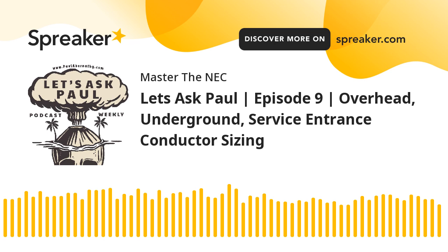Now, ironically, somebody said to me, Paul, what if I have no continuous loads and no conditions of use, no adjustment or corrections involved? Then you simply size your conductor based on your calculated load, and that's it. And of course, you're going to go to your terminal limitations. If no other information is given, and it's 100 amps or more, you go to the 75 degree column. If it's less than 100 amps, you go to the 60 degree column. Pretty straightforward, right? But we're not done yet.